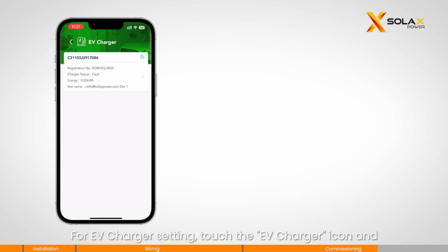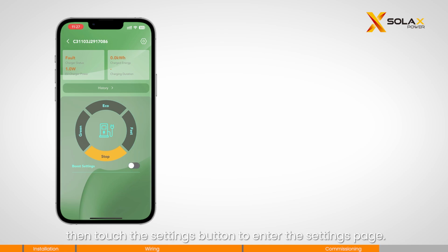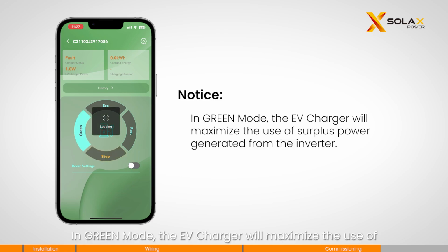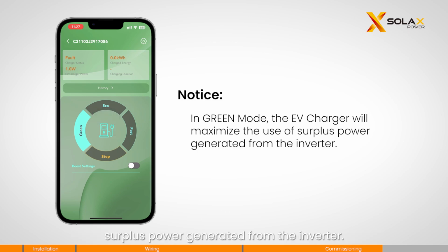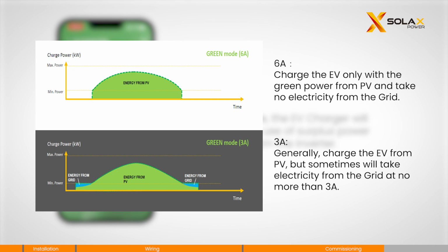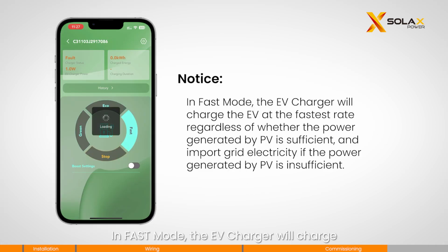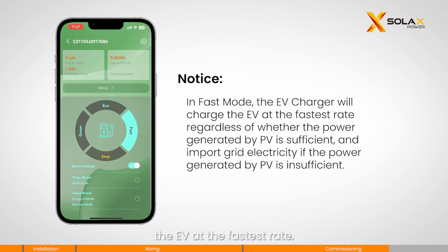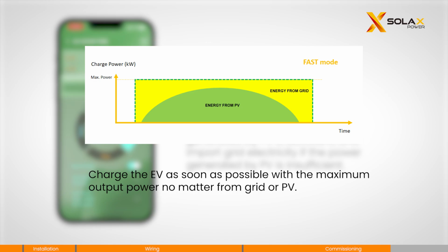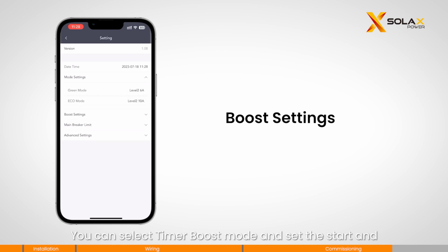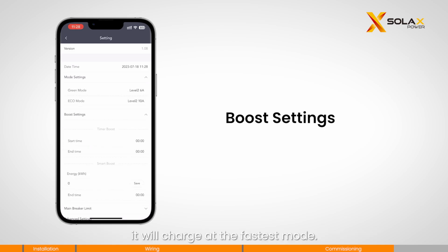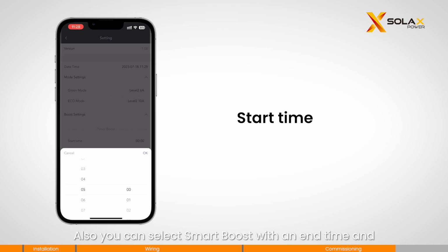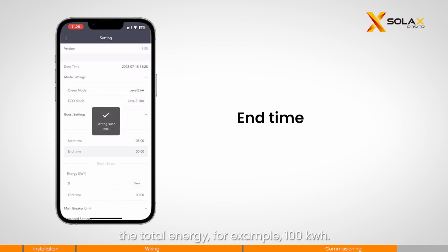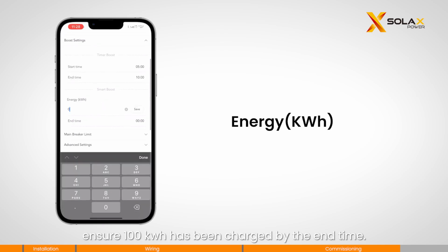For EV charger setting, touch the EV charger icon and then touch the settings button to enter the settings page. In green mode, the EV charger will maximize the use of surplus power generated from the inverter. In eco mode, it helps users to charge at a minimum power rate. In fast mode, the EV charger will charge the EV at the fastest rate. You can select timer boost mode and set the start and end time for the charger. During this period, it will charge at the fastest mode. Also, you can select smart boost with an end time and the total energy, for example, 100 kilowatt hours. The system will use the PV energy in priority and ensure 100 kilowatt hours has been charged by the end time.